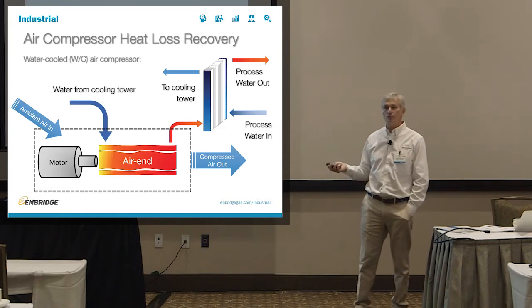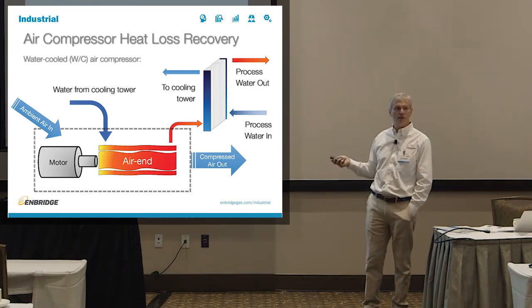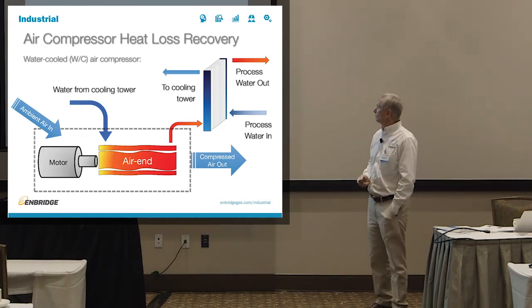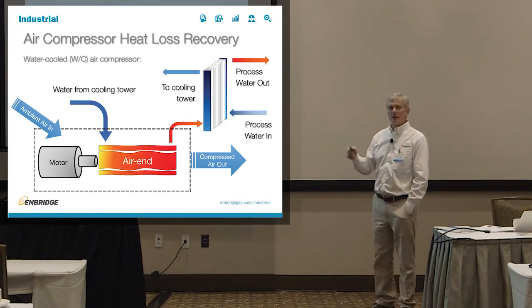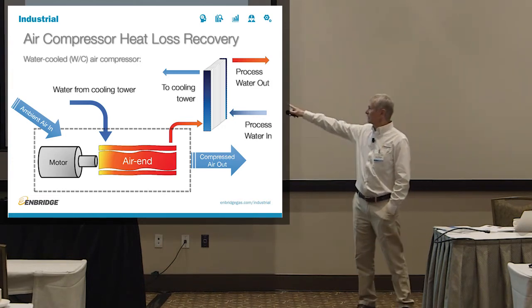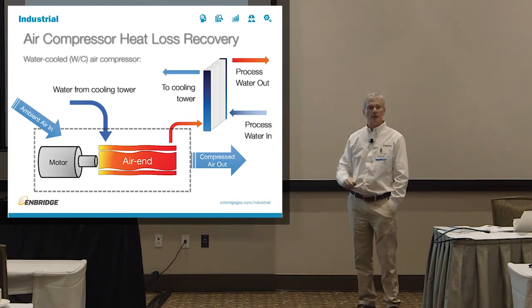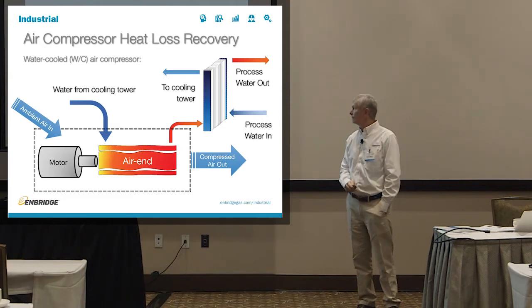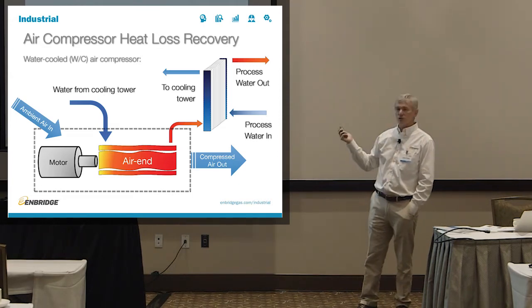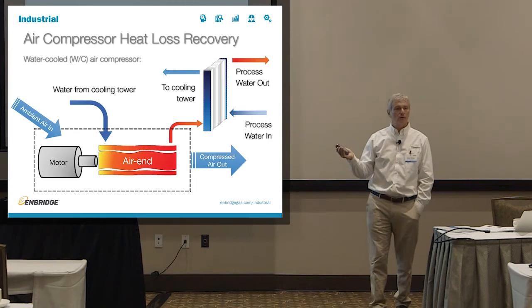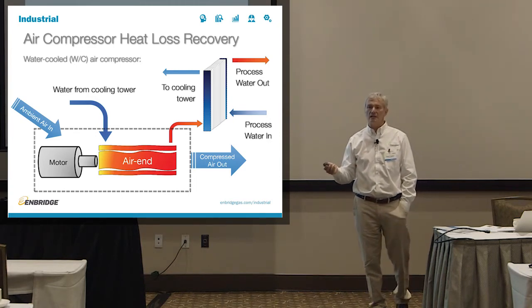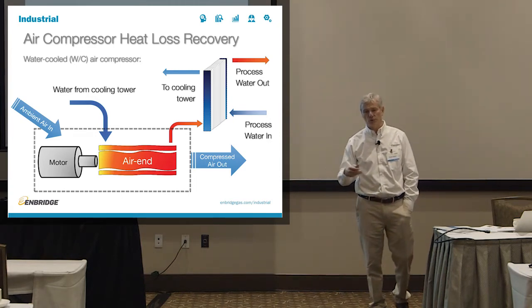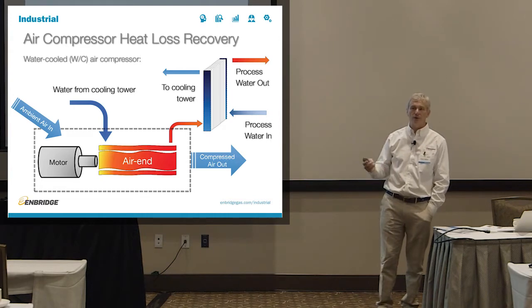If you have a 300 horsepower compressor, there is a lot of heat going in there. And then send it back to the cooling tower rather than sending really hot water back to the cooling tower directly. You can use it for the process water in or out. You can use it for any other heat sink that you have available. You can use it, for example, for the glycol loop if you have a makeup air unit or something like that.